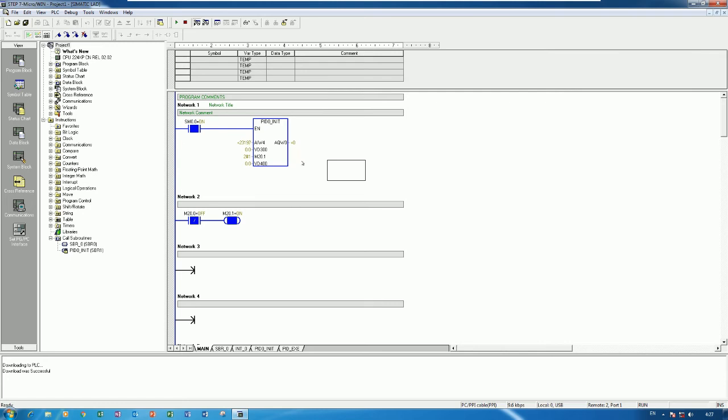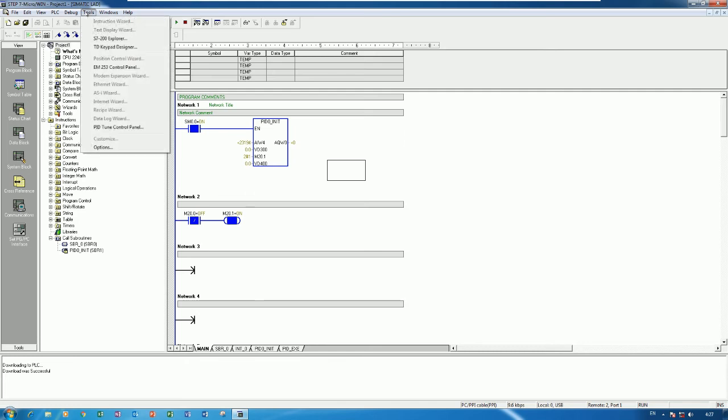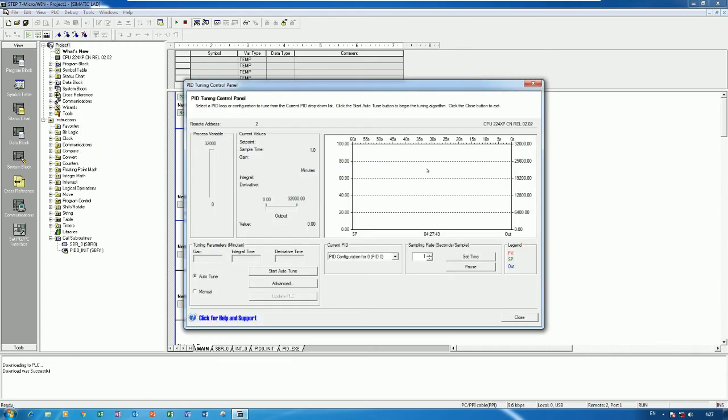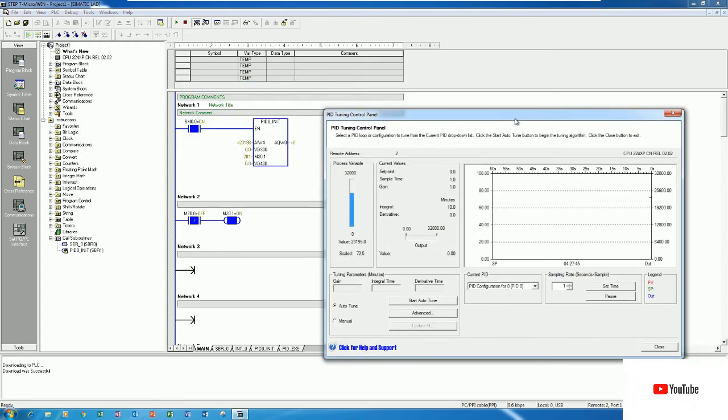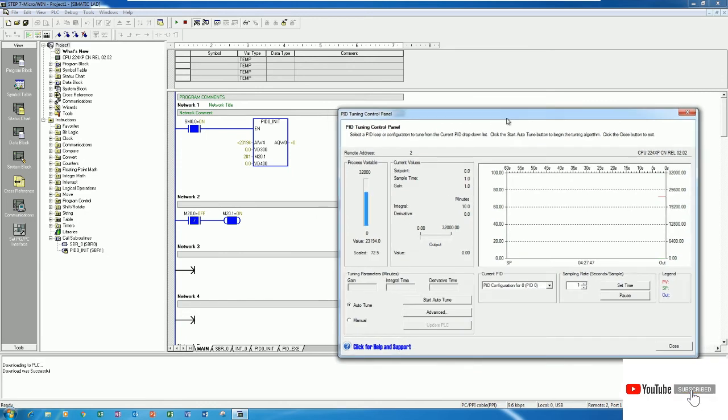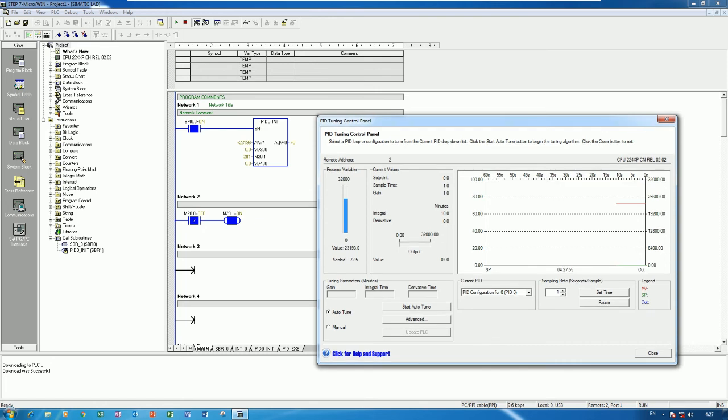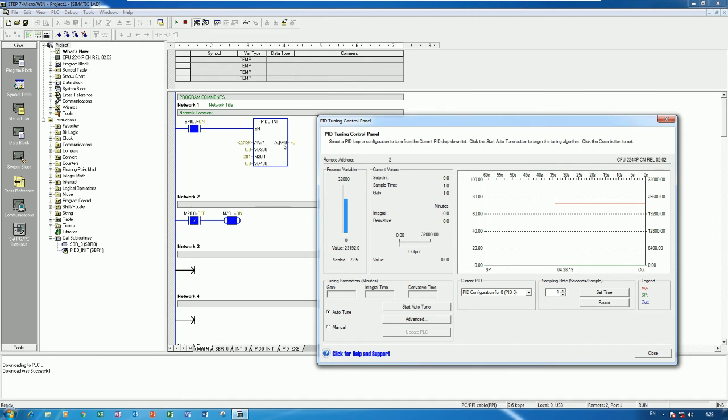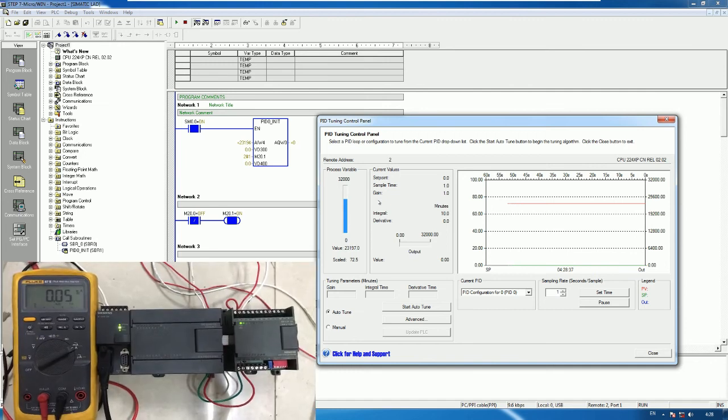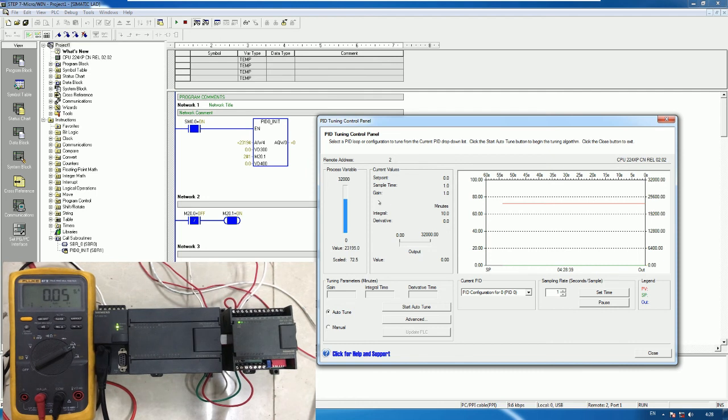And I will go to PID tune control panel. I will go to PID tune control panel. So here is the PID tuning control panel. We have a PV, process variable, and have the set point. And this is a scale 0 to 32,000 for output for control the VSD or electrical devices. We are analog output. So I will show the analog output right now, so 0. You see right now the analog output is show 0.